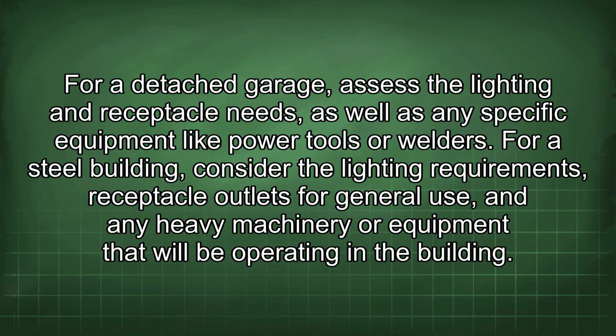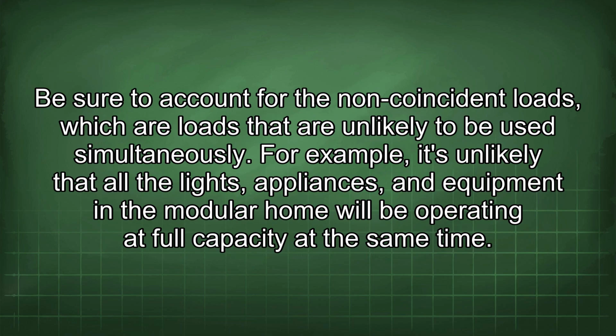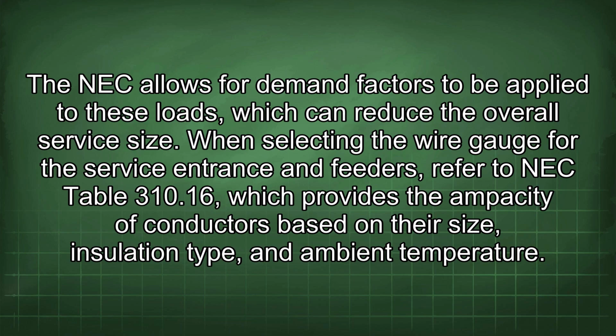For a steel building, consider the lighting requirements, receptacle outlets for general use, and any heavy machinery or equipment that will be operating in the building. Be sure to account for the non-coincident loads, which are loads that are unlikely to be used simultaneously. For example, it's unlikely that all the lights, appliances, and equipment in the modular home will be operating at full capacity at the same time. The NEC allows for demand factors to be applied to these loads, which can reduce the overall service size.